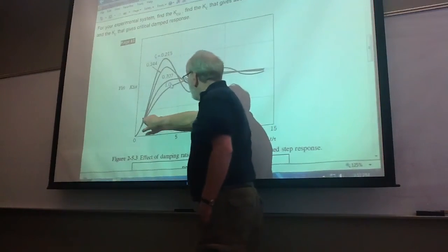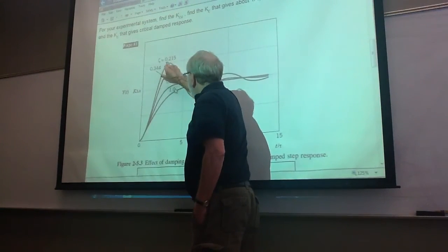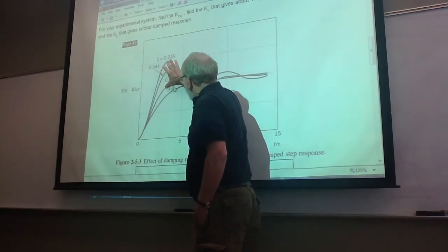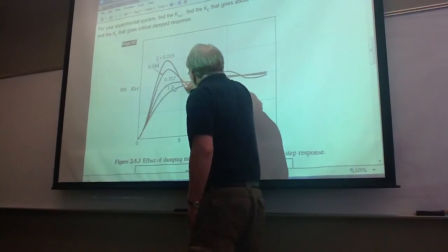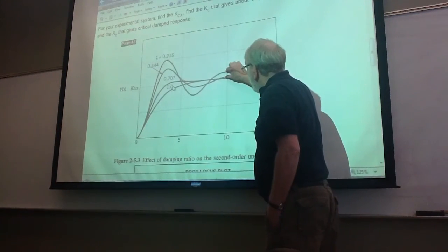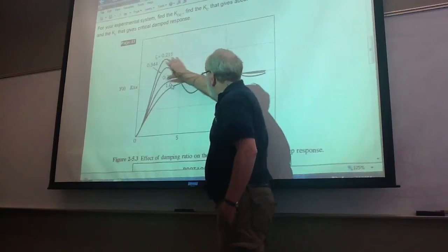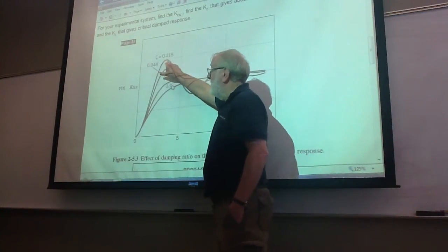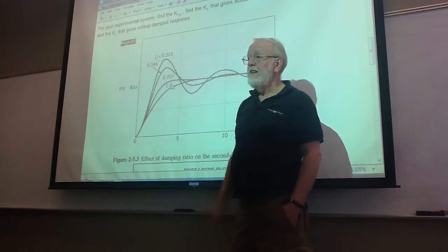Here's one that goes way over. In fact, it goes 50% over. This is 100% here. That goes 50% over, comes down, comes in. This is 1/4 as high as this. We have a magic name for that one there. It's called quarter decay. Everybody say quarter decay.